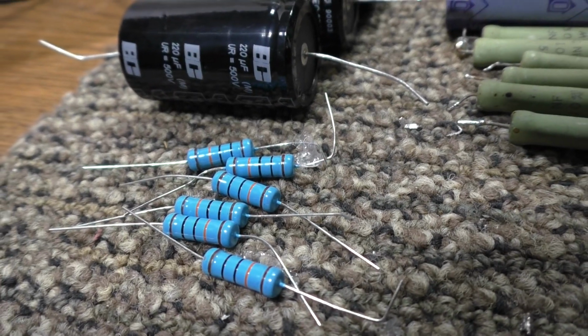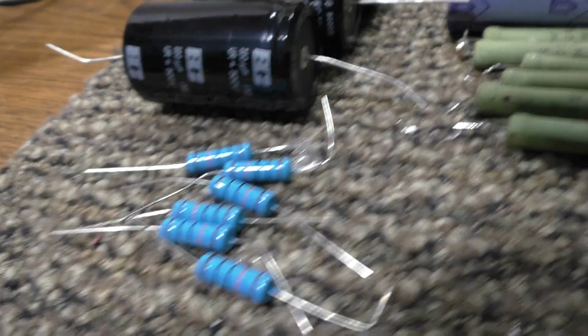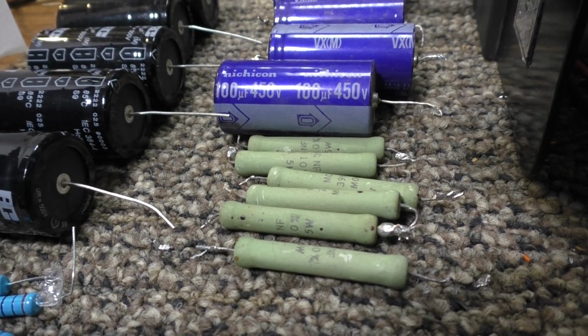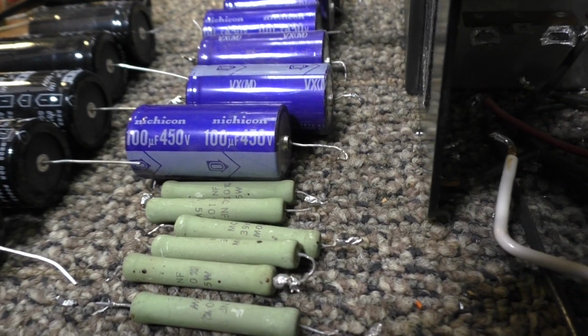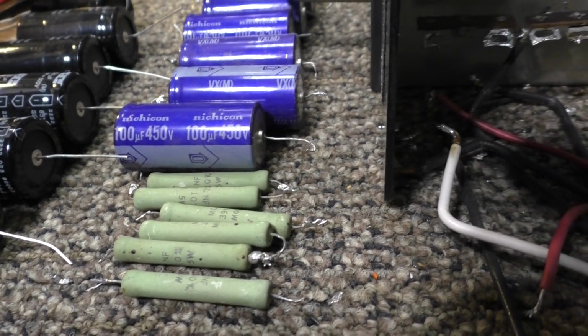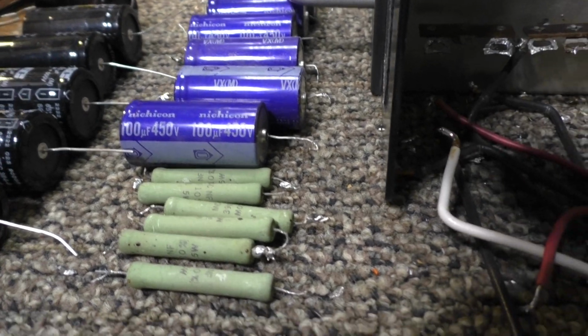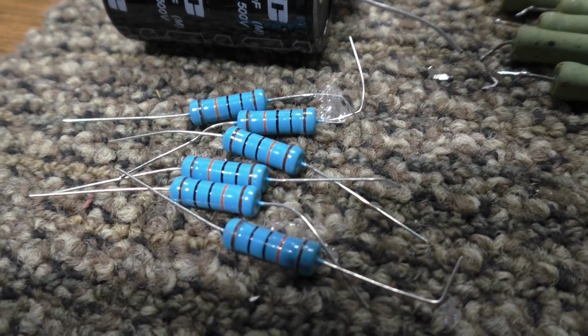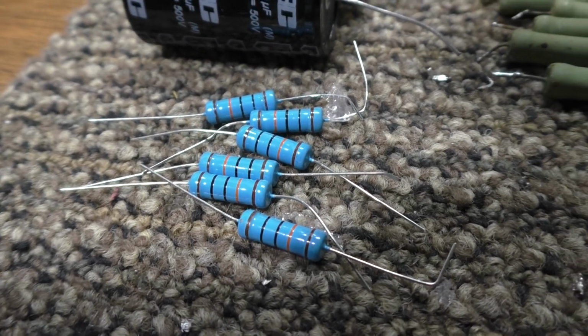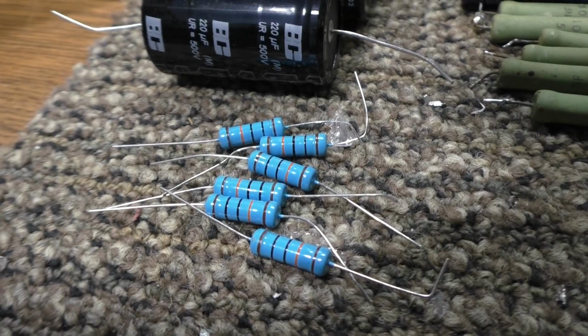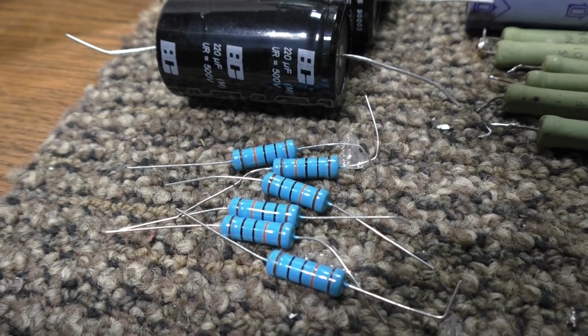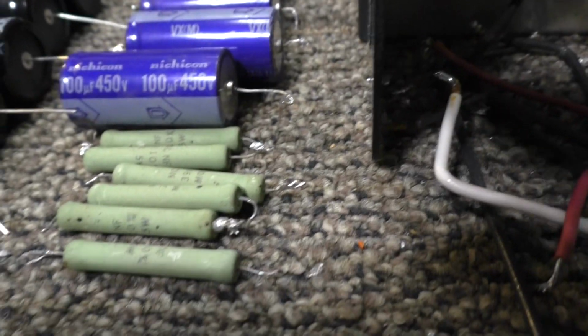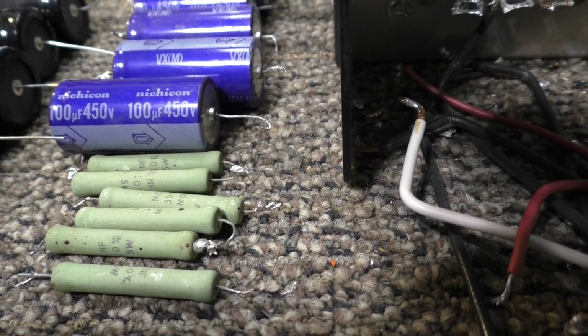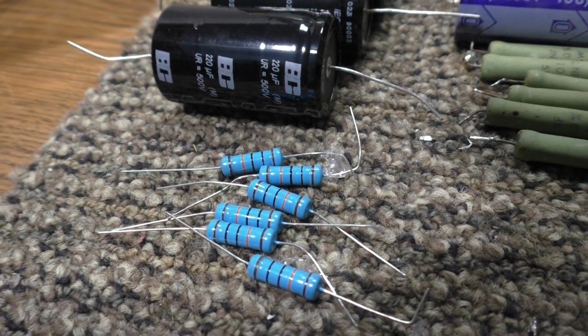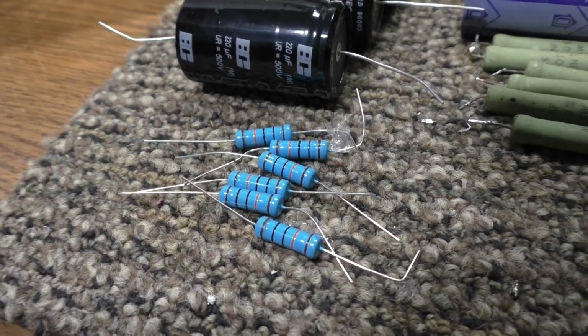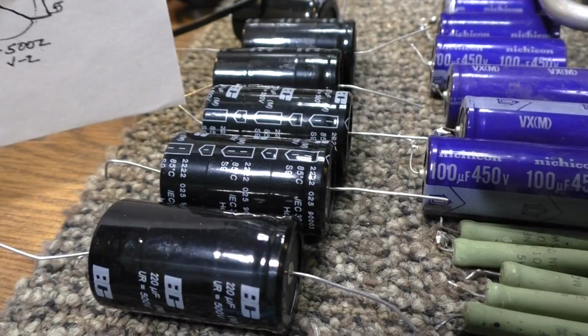And these are 3 watt bleeders. Originally, the 5 watt bleeders at 39K were drawing 5.12 watts, so those were overused for their rating. Now we're going down to 3 watt bleeders, but since we're upping the resistance to 100K, it's only going to draw about half, about 1.5 watts per bleeder. So that's going to cut the bleed's wasted power and heat from 30 watts down to about 9 watts, 1.5 times 6. So it's less heat, less wasted power, and more capacitance.